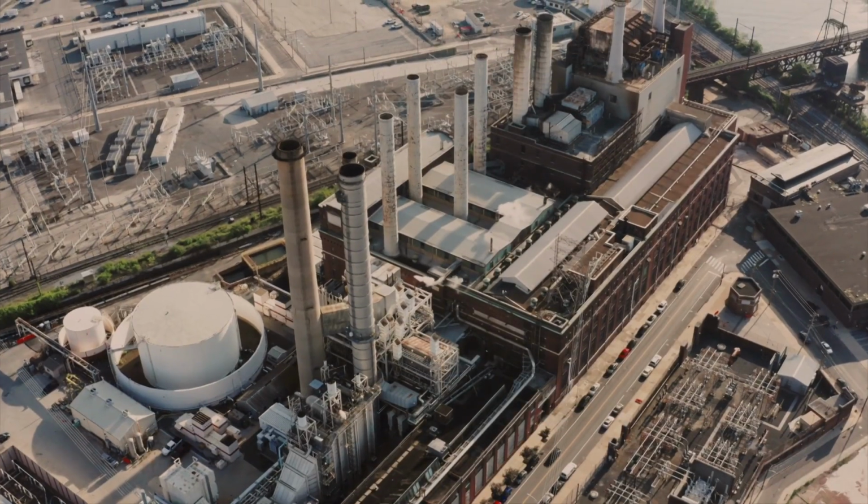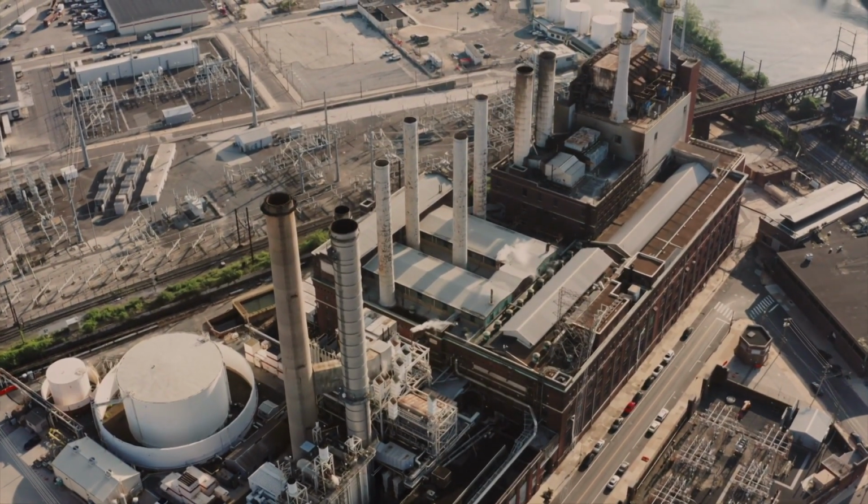So, in this arrangement, the gas turbine can be decoupled from the operation of the steam turbine, allowing the steam turbine to shut down with continued gas turbine operation. It is always desirable that the exhaust temperature of the gas turbine should be above 570 degrees Celsius, otherwise the steam cycle will be insufficient, resulting in lower combined cycle efficiency.